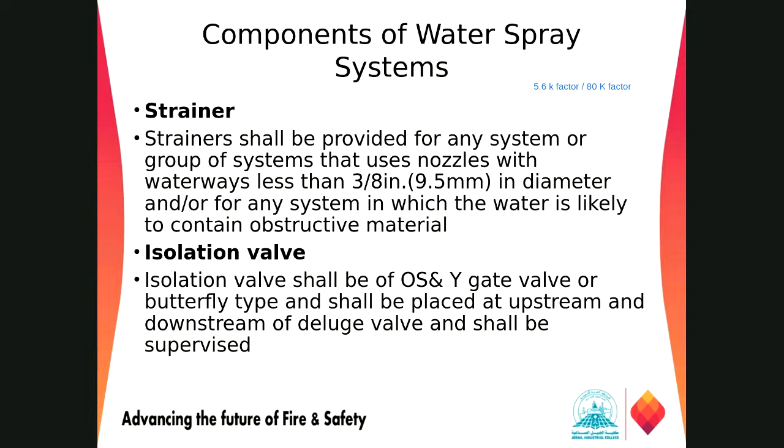But with the water spray nozzles, we have a K factor of around 1.2, 1.4, 1.5, very small nozzles, because we don't want to control the fire first. We just want to cool the surface by discharging a drop of water all over the surface, and we have all nozzles open at this moment. So if all nozzles are open and the orifice is of a larger size, we might need more than 10,000 GPM for one equipment, or even more than that, which is not possible. This is just for cooling the surface, and that density is more than enough to control the fire.